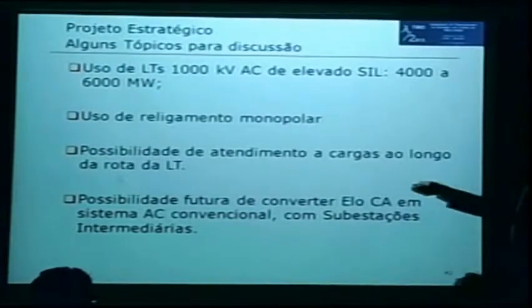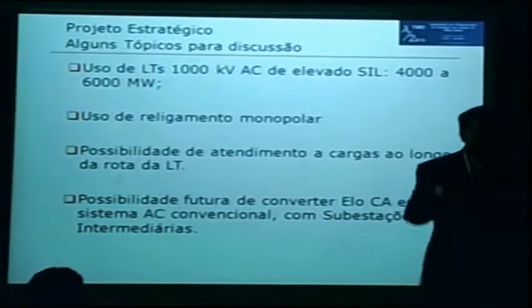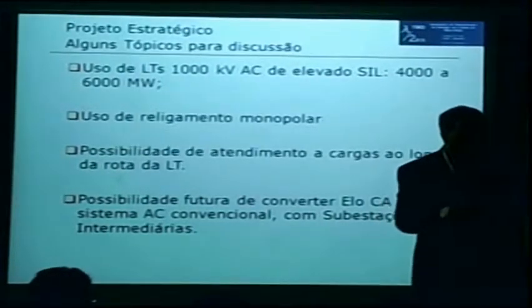So with a 1,000 kV line, we can transmit 4,000 to 6,000 megawatts. This is the block of energy we want to transmit with half wavelength using single pole reconnection. For that, we're going to talk with experts from China who are dedicating their time to studying single pole reconnection, because you maintain flow in other phases, solving instability and supply of energy problems.